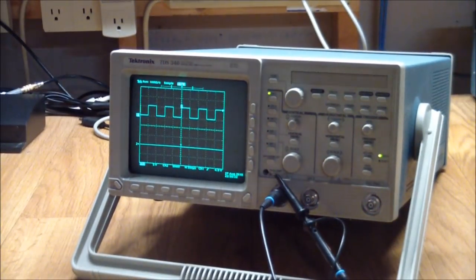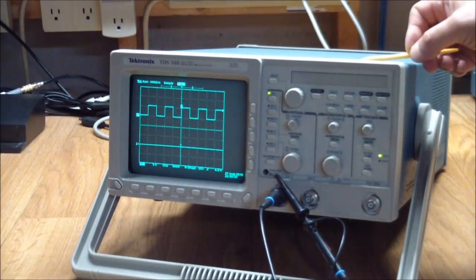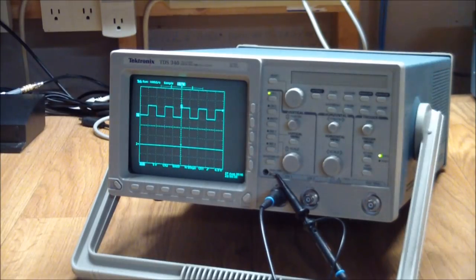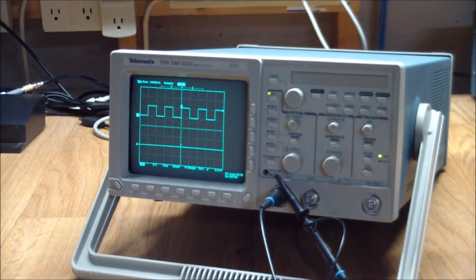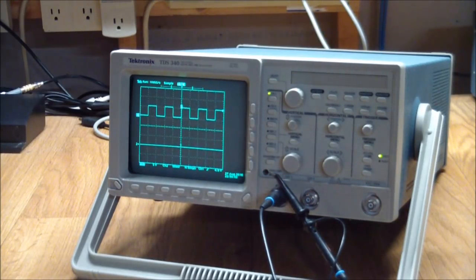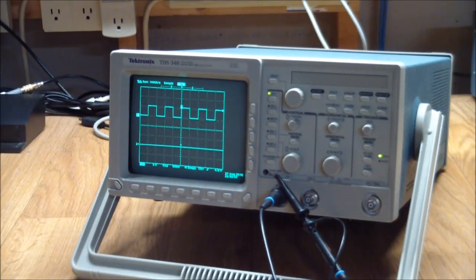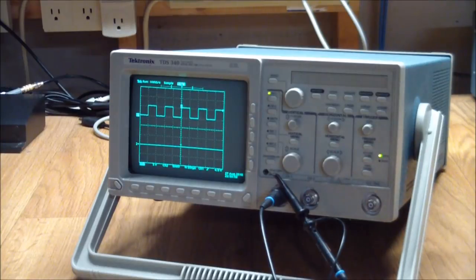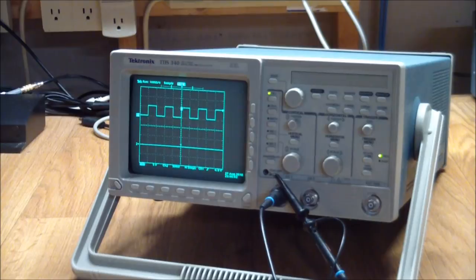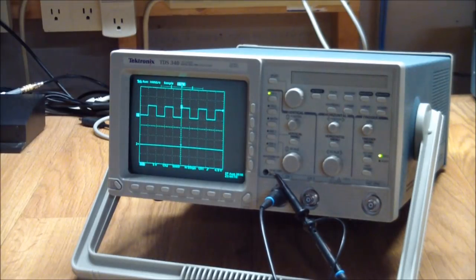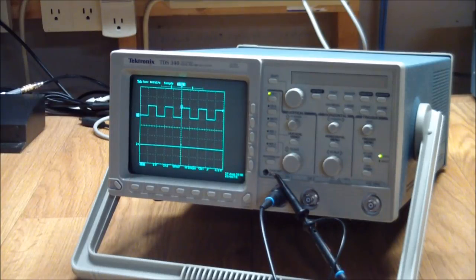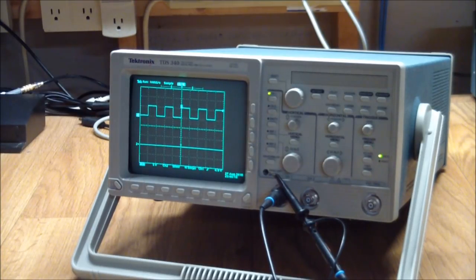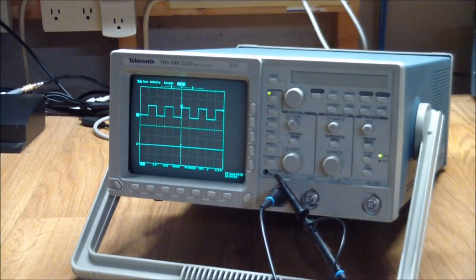So what remains to be done is not much. I mean one of the things was this thing was completely clean. Normally stuff out of the university has stickers all over it, calibration stickers, inventory stickers, all that sort of stuff. This one was completely clean so it looks like somebody had this in their own personal lab for a while and removed all traces of where it came from. But when it decided to not work anymore it ended up at the university salvage again. Of course what some of you may be thinking is I left out something big that needs to be done and that is to go through and recap the whole thing. And eventually that needs to be done especially in the power supply but for now everything is running just fine. And as I've mentioned before I usually won't go in and wholesale replace everything after visual inspection and checking the caps with the meter doesn't reveal any obvious problems. I leave it the way it is.